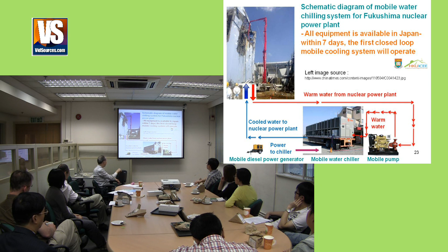Remember we talked about 1.6 megawatt cooling capacity, so we can work out 6 sets of 1.65 megawatt, that's about 10 megawatt, roughly matching the decay heat. So if we want to work with one reactor, we'd need 6 sets of this. For 3 reactors, multiply by 3. So that's not difficult.